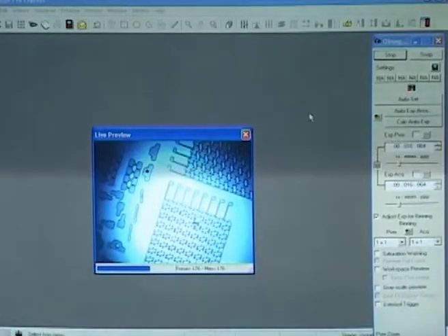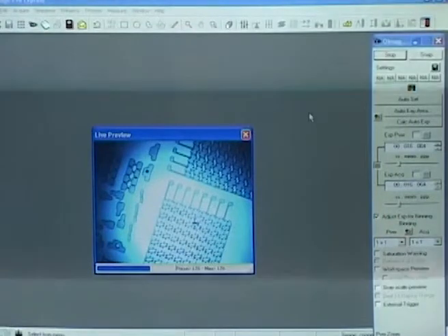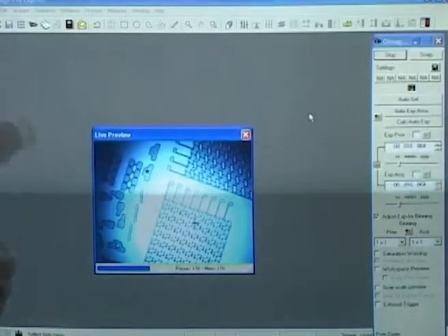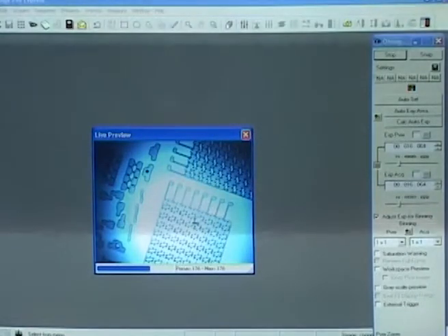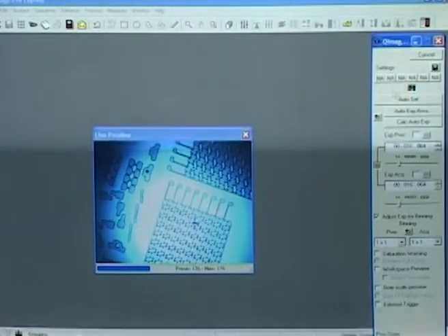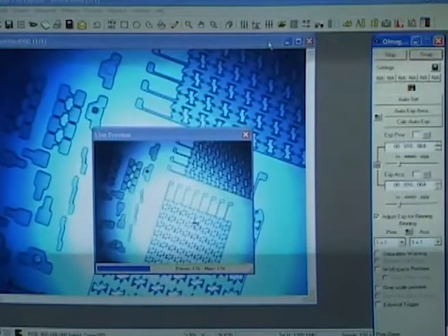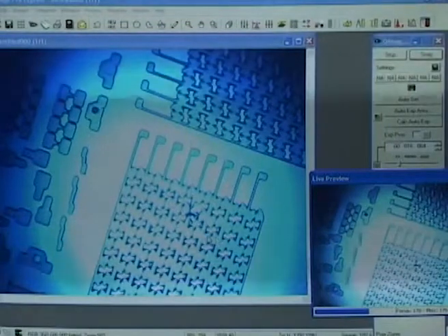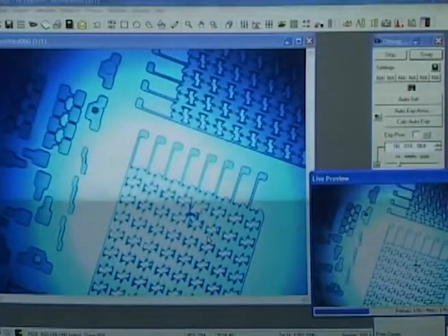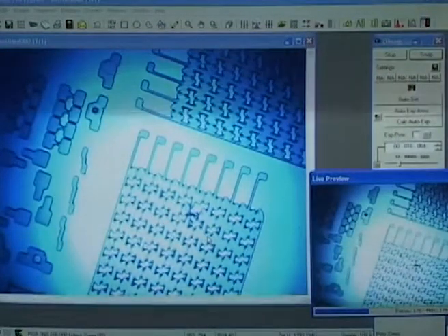Now this is probably one of the best foci that one can get using these images, because I have already calibrated it using the eyepiece. Okay. Now I am going to store this image. So I go to the snap option here, and automatically a photograph is generated, as you can see, which gives you a digital image of what has been captured from the CCD camera.